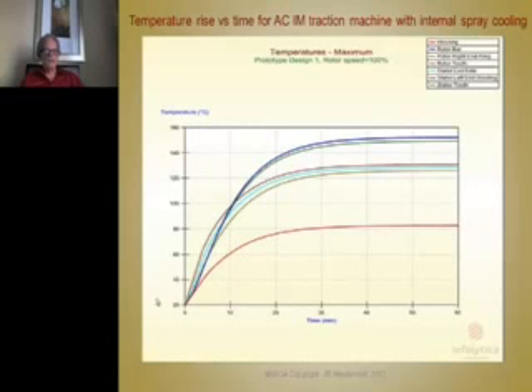There's a left end winding and a right end winding, and you notice how at startup the thermal time constant of some of the components is different than the other. They actually cross over here. The stator left winding actually heated up first, and then as the cooling affected versus its mass, it actually cooled down a bit. And this blue, and what's the blue? I guess it's the rotor bars. They didn't cool. That's what limits the temperature of this machine, the rotor bars, not the stator conductor. So that's the type of analysis you have to do to really predict what the motor is going to do. Either use a lumped parameter method to do this or a finite element method. So that concludes this last thermal article. Thank you.